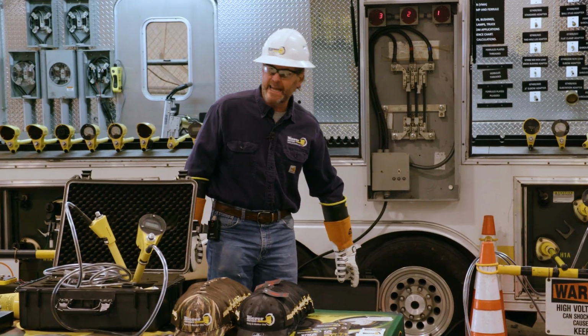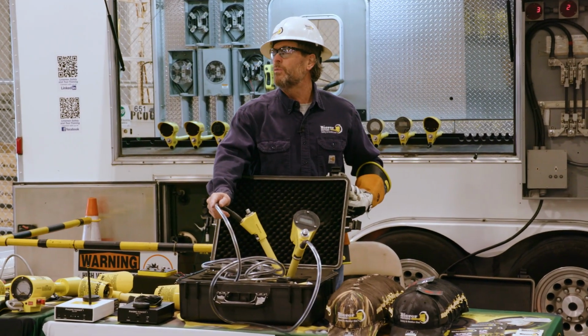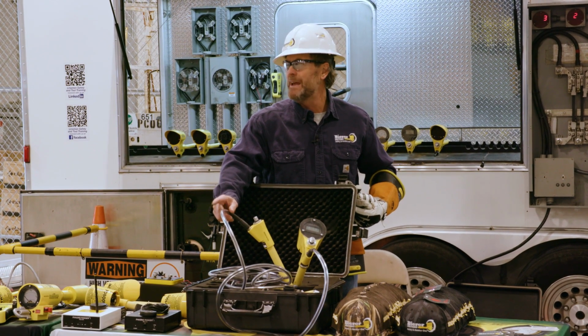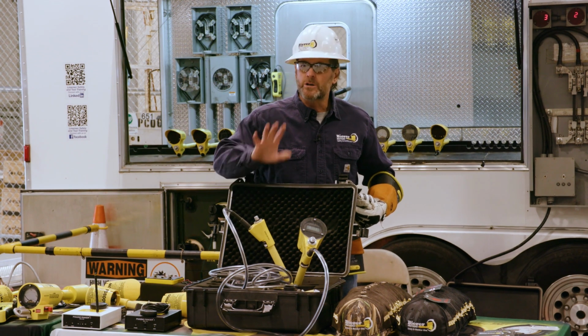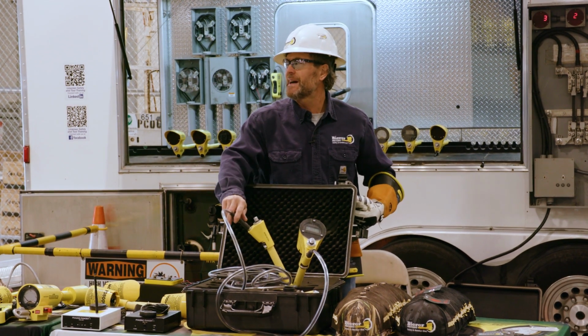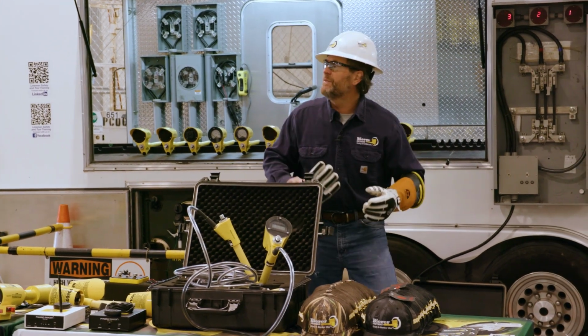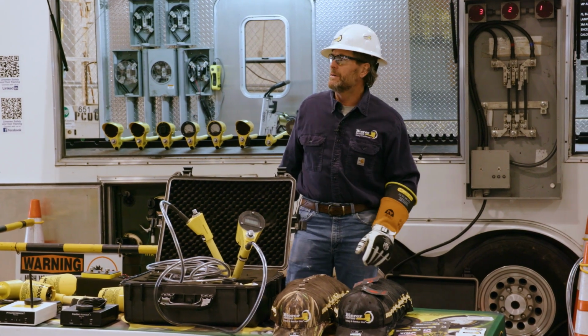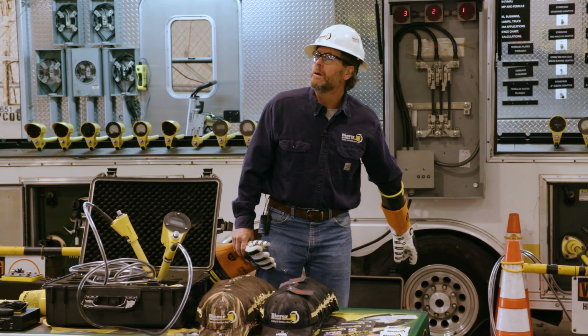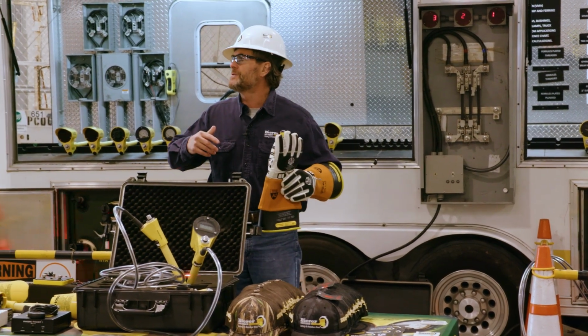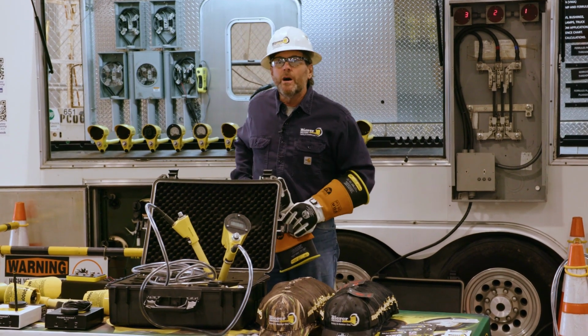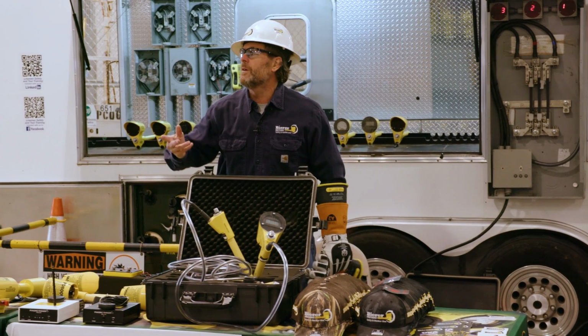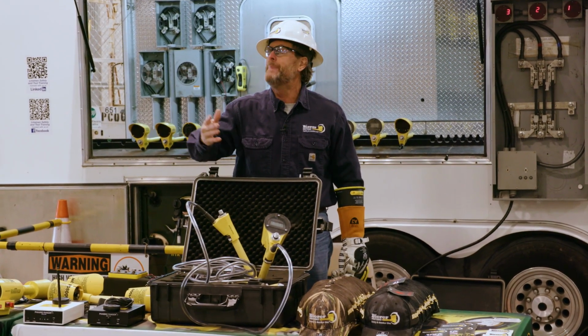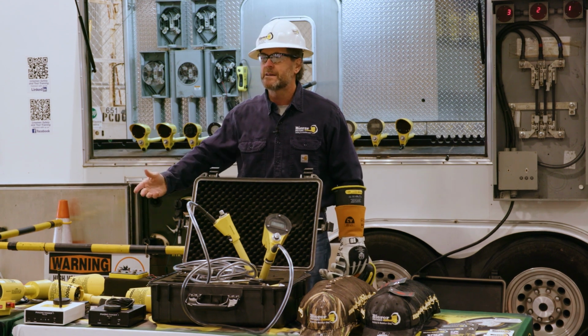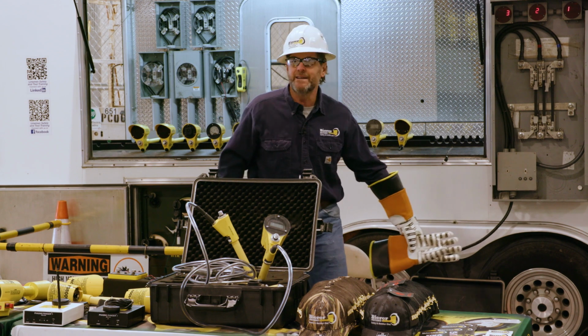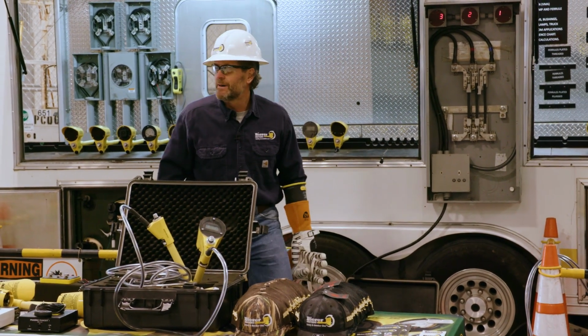And you can hear that cable buzz. This cable — we're the only company in the world that builds a cable within a cable. Nobody else does this. So all of our corded tools are shielded to 35,000 volts. So when we high-pot or phase using this tool, the cord can lay on the ground, but you want to stay away from that cord. It's part of the tool. Remember what we talked about, your air dielectric — if you're to stay 31 or 36 inches back from the meter head, you'll also want to train and teach that you stay that same distance back away from the cord. Make sense? Because that's part of the tool. It's energized, you can hear that? See, Robbie says it's energized because he can hear it's energized.